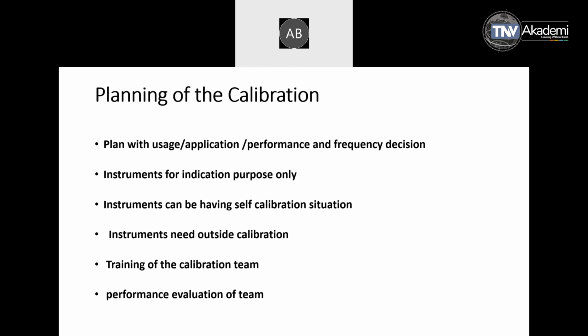He may check it with some slip gauges which are already approved, depending upon the dimension of the item he is going to check. But it is very important that this instrument is used with a test block so that the readings are correct.